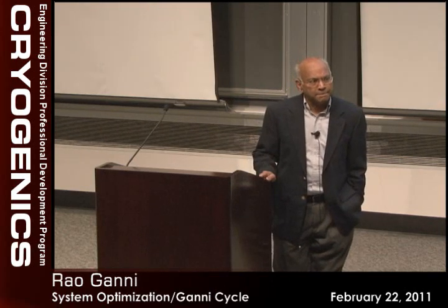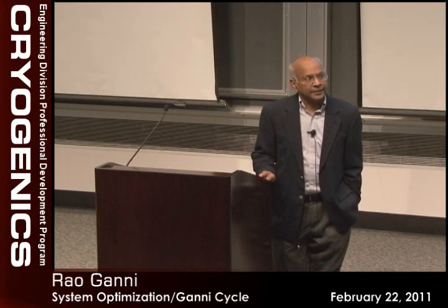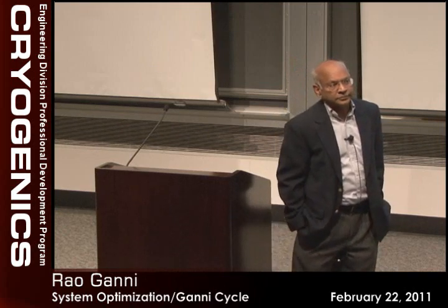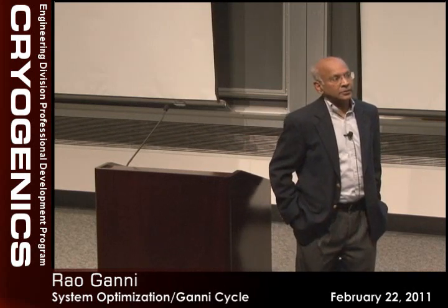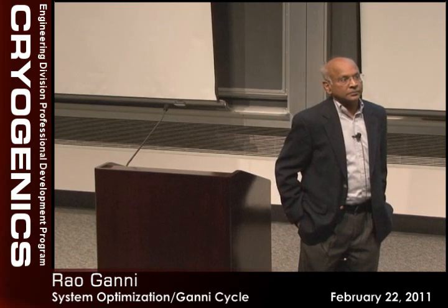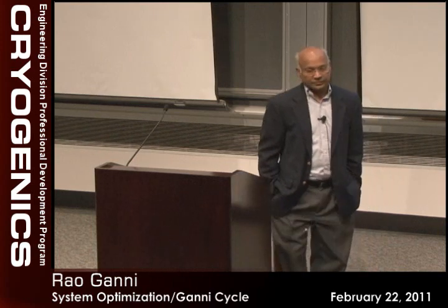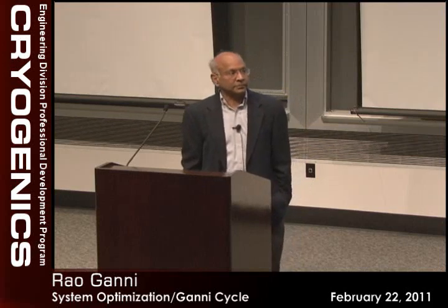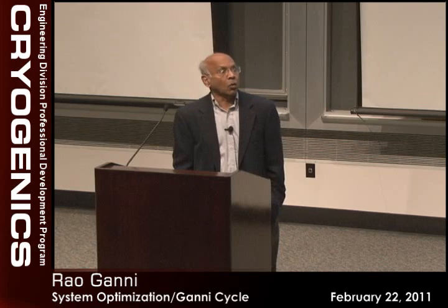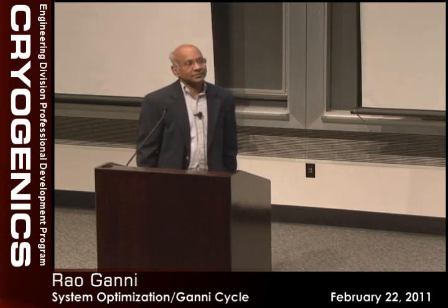Yeah. I just want to add one more comment. You made the gain in power consumption for the plant. In my opinion, the biggest gain is also due to the reliability increase. Although we could not evaluate it exactly, based on my experience running with that, I think we gained more money even than the power. They save a lot of money on maintenance, and that's just by leaving the plant alone.